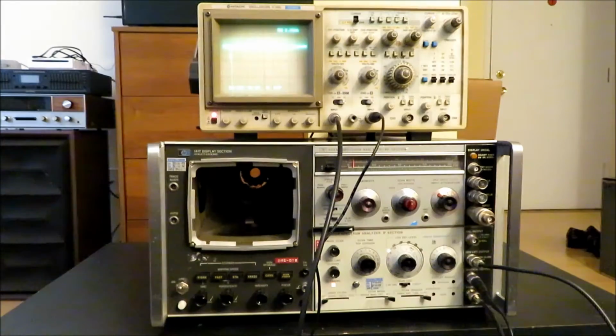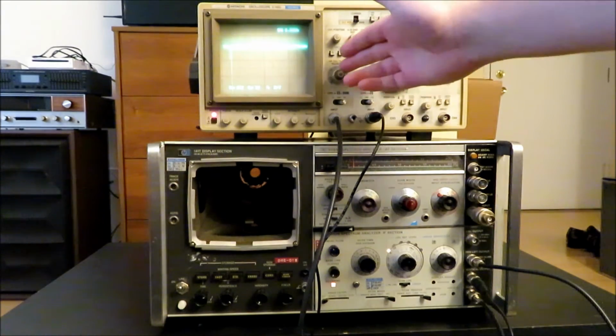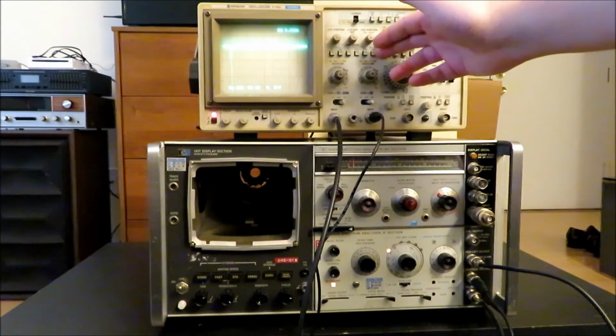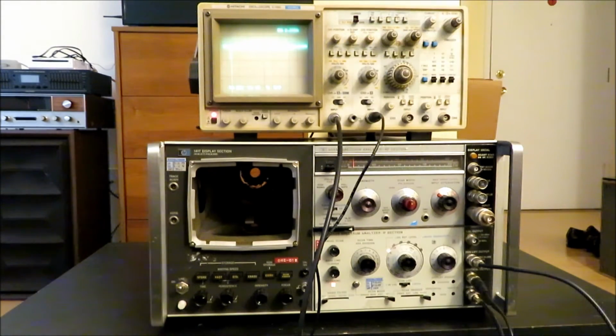So now, with the fuses replaced in our plugins and the plugins back in the unit, we have the unit hooked up, and you're going to want to have the vertical scaling of channel 1 set to 10 volts per division, and your Y channel, or channel 2, set to 1 volt per division. This will pretty closely match the horizontal and vertical scaling of the 141T's display. If you want to adjust that more finely, you can use the verniers on your oscilloscope, if you know how to use those and want to.